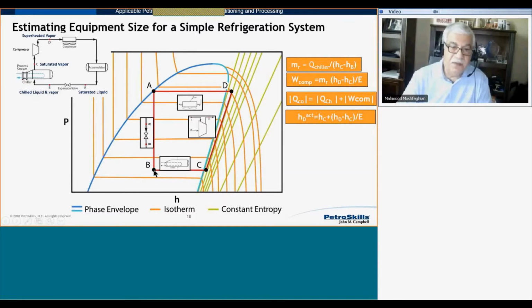So I'm in the chiller, I'm in two phase. Any point within the phase envelope here is two phase. So I enter the valve as saturated liquid, I get out of the valve and enter the chiller as two phase. This line represents the fraction of liquid, and this segment represents the fraction of vapor. So the further to the left the point is, the higher the fraction of liquid and the less vapor.